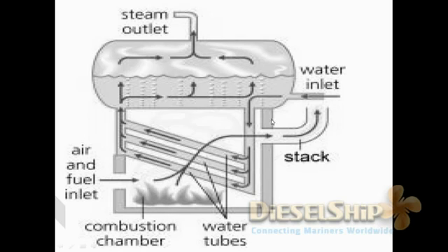So the previous design of the boiler had internal downcomers, with which the cold water after the feed water inlet enters the internal downcomer, and then as it gets heated up, its density decreases and it forms steam, and then rises up the risers and gets collected in the steam space. Let's see another picture and understand the design concept and what design changes were made in the recent generation boiler.